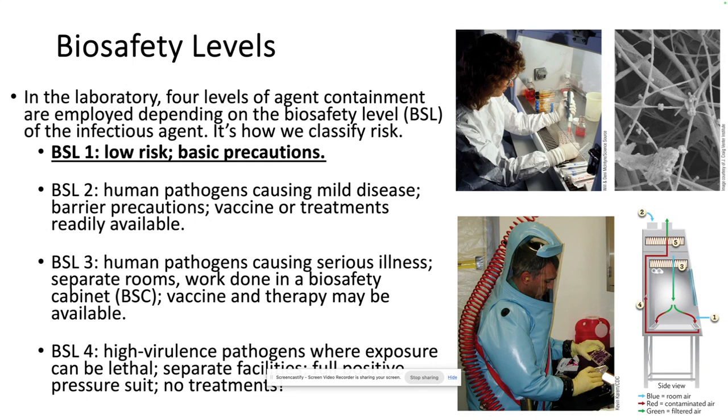So a biosafety level 3 lab is actually going to be a separate room in a building from the level 2 and level 1 biolabs. Okay, so it's going to have its own ventilation system as a precaution, as well as the biosafety cabinet. Now, with a level 4 biolab, those labs are going to be in completely separate facilities. They're going to have their own building on the laboratory campus.